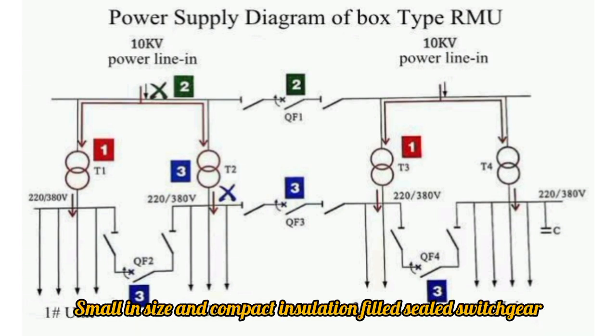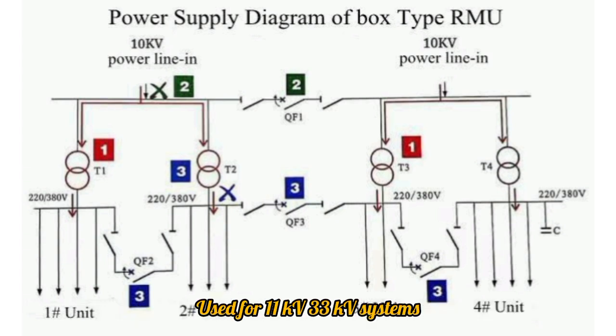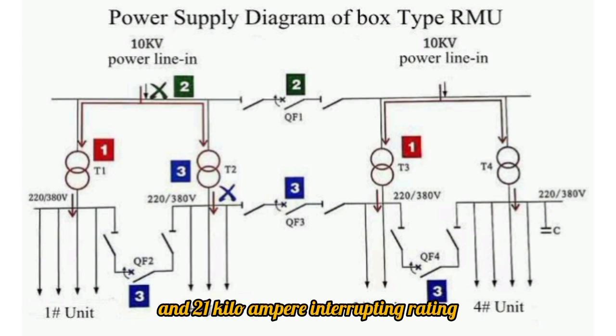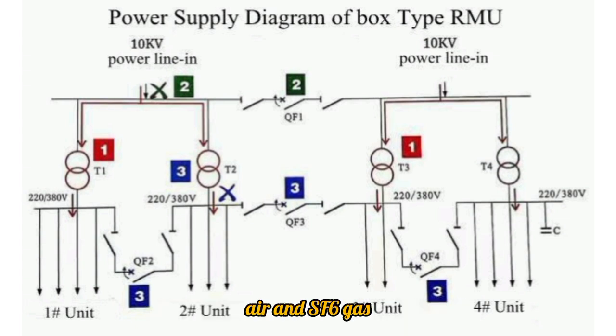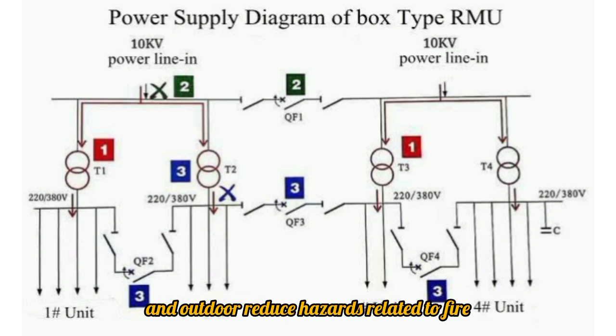Small in size and compact insulation-filled sealed switchgear. Used for 11 kV and 33 kV systems. Normally rated for 630 ampere and 21 kA interrupting rating. Comprises three types of insulation: oil, air and SF6 gas. SF6 gas insulation is widely used, normally has two incoming and one outgoing and vice versa. Have separate protective and measuring devices. Can be used indoor and outdoor, reducing hazards related to fire.